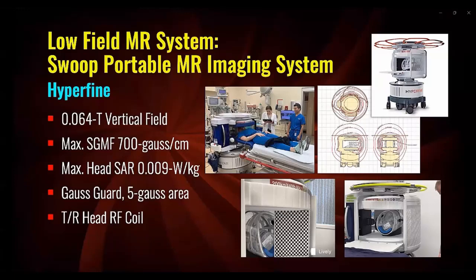Because of its innovative design, there are no major issues related to ferromagnetic objects becoming missiles or projectiles, as shown by this box cutter and fire extinguisher, both made of ferromagnetic materials. Watch what happens when these items are brought close to the Swoop MR system. For the box cutter, there is barely any attraction to the 0.064 static magnetic field, while the fire extinguisher exhibits virtually no magnetic field related issues.